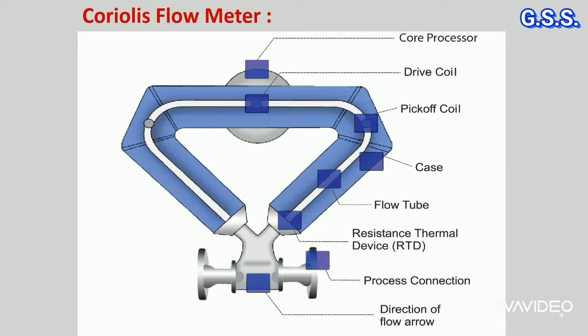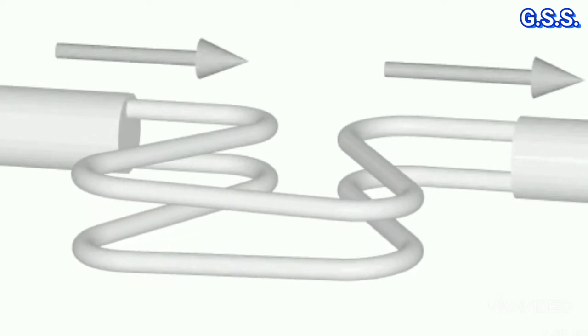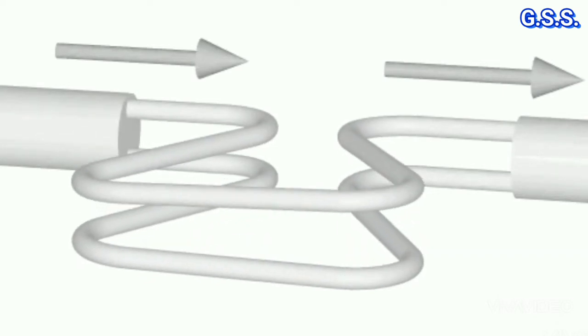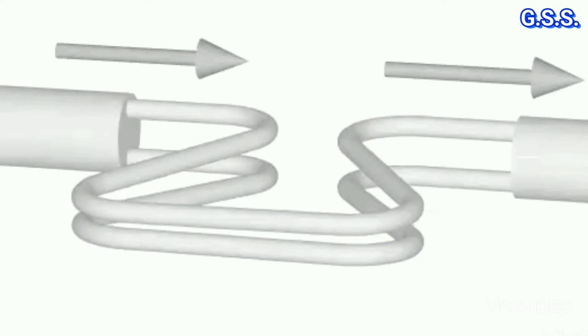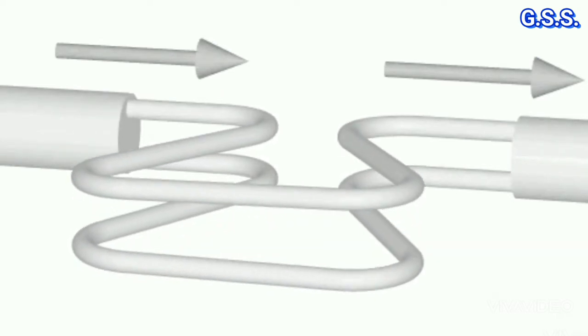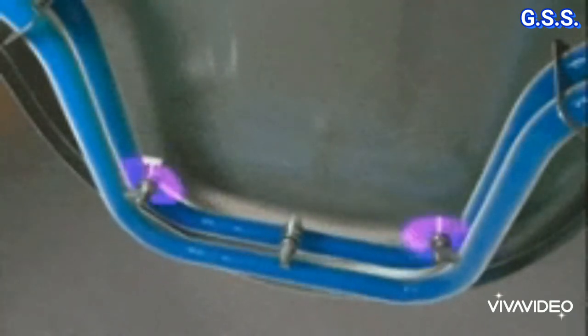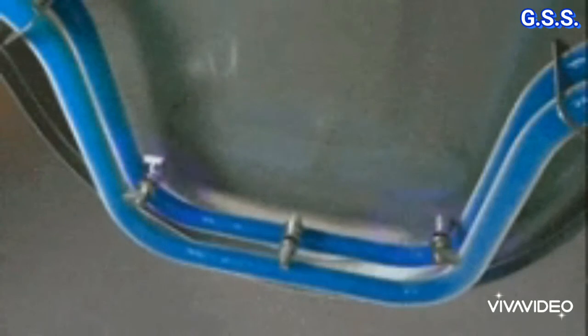Coriolis flow meter measures mass flow rate. It works based on the inertia caused by fluid flowing through the oscillating tubes. Due to that inertia, oscillating tubes are twisted, which is proportional to the mass flow rate. This twisting of oscillating tubes is measured by a sensor to generate a linear flow signal.